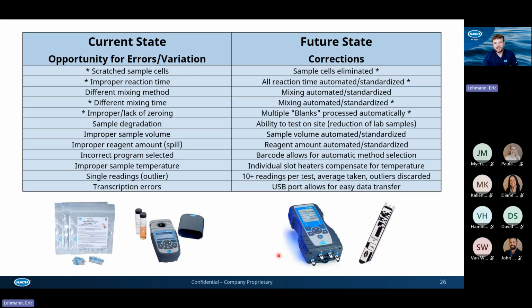The SL1000 doesn't use sample cells, right? So that's eliminated. We don't have to worry about that. We don't have to worry about wiping down those sample cells. Improper reaction time. So say we have an operator testing total chlorine. Are they going to wait the full 3 minutes? Maybe they get impatient. Let's just wait 2 minutes, we'll be good. Or maybe they forget about it and wait 5 minutes. With the SL1000, that's going to eliminate that problem.